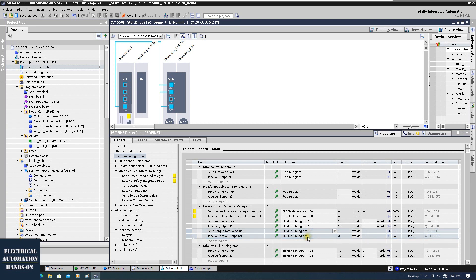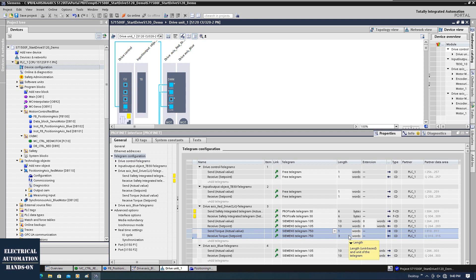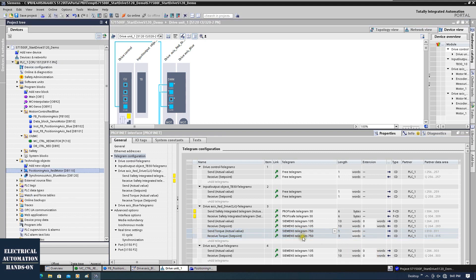Then you will find telegram 750 here. It has an actual value and a setpoint. The actual value has one word, so it can feed back the actual torque value in Newton-meters. The setpoint lets us set the high and low limitation, because torque has a direction — when the motor runs forward, torque is positive; backward is negative.